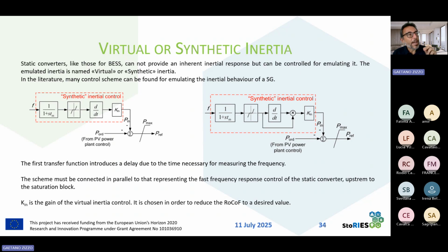So in this case, we have a specific control of the VSC converter of the storage system. We can also use a supercapacitor, for example, not necessarily batteries. And this new control is represented in different ways. You find in this slide two different implementations of the synthetic inertia control that allow the battery storage system to provide not only fast frequency regulation that is activated by frequency differences, but also to provide a virtual inertia to simulate the inertia of a rotating machine activated by the value of the ROCOF, so activated by the variation, the derivative of the frequency in time.